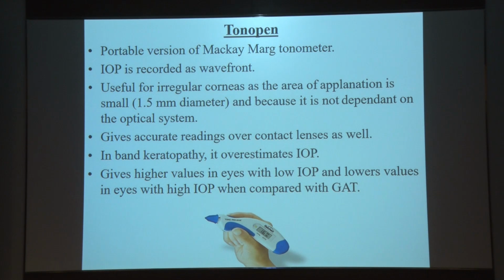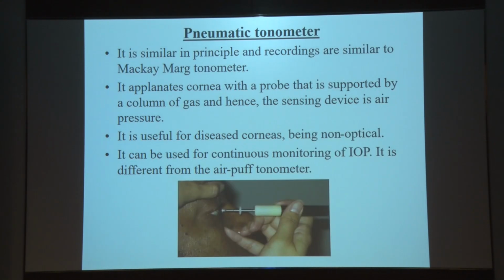It gives accurate readings over contact lens as well. In band keratopathy, it overestimates the IOP. It gives higher values in eyes with low IOP and lower values in eyes with high IOP when compared to the Goldmann applanation tonometer.